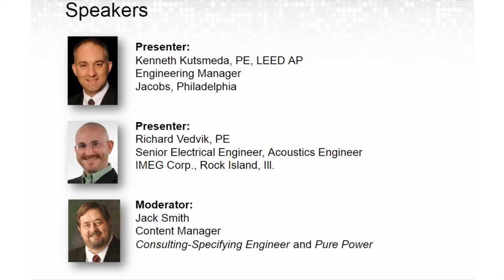Okay, Rich, next question's for you. Actually, it's a request to discuss the issues between UPSs and generators, and why a UPS may not transfer from battery power to generator power. Thanks, Jack. So I've experienced this in the past, where a UPS has a requirement for the power quality that comes in. There's a limit at which harmonics within the incoming power can prevent that UPS from wanting to connect to that source. It basically sees it as low quality or unusable.